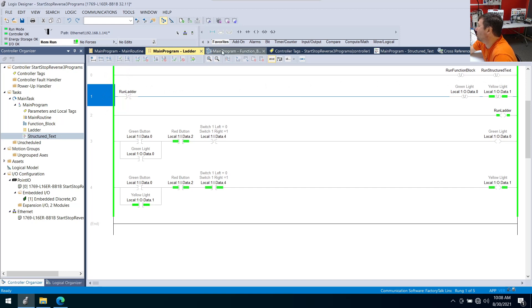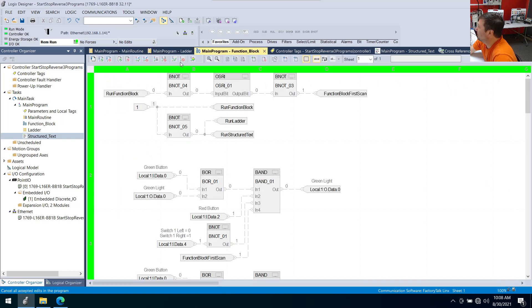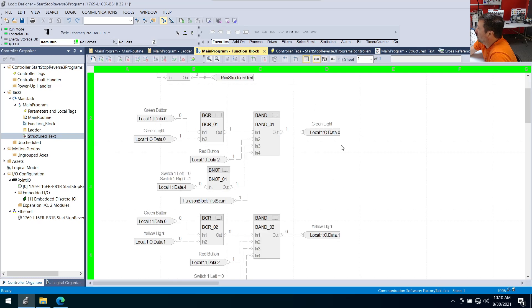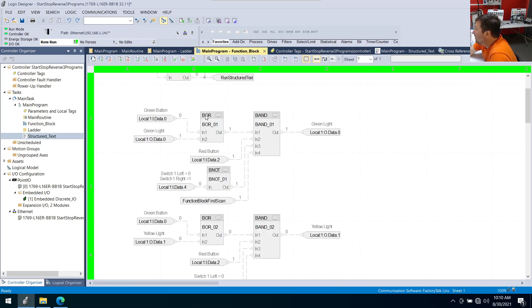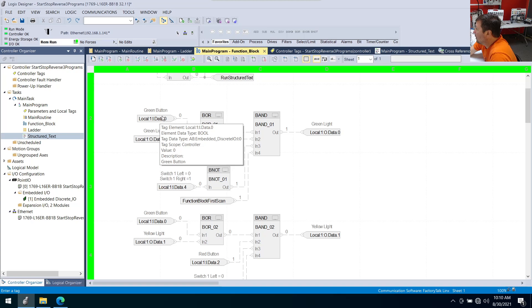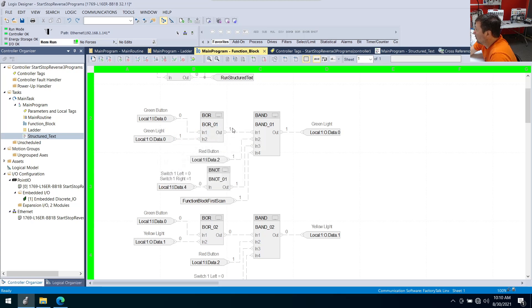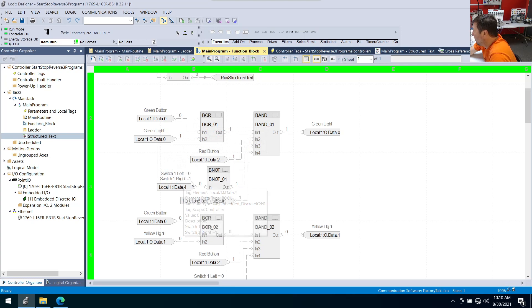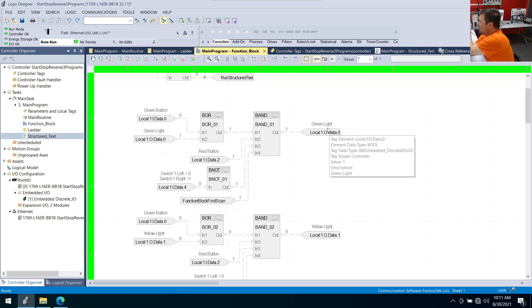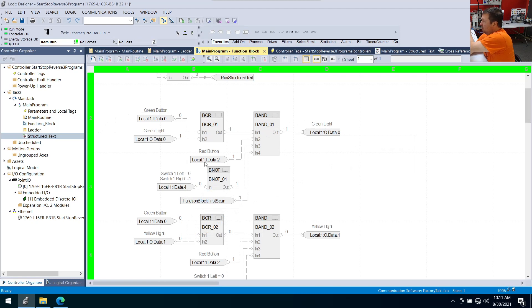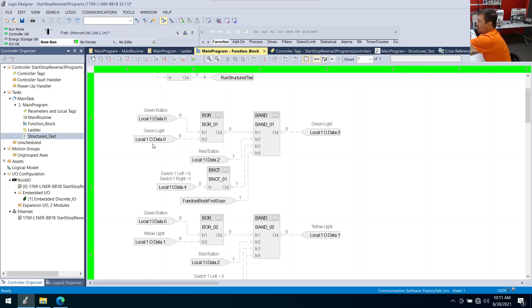Now let's look at our function block routine. So here's the function block logic, and let's skip over this first one for now. And right here is our green light logic. So right now we have a one in our green light because we're still running the ladder routine. If I go over here to our main routine, you can see I've got switch four in the left position. So if the green button or the green light is on, we're going to get a one here. And then we're looking for that and the red button and not switch four to the right position, and then not this first scan block. And so when I switch over to function block with switch four, you're going to see the green light go out. So there it goes out. And now we press the green button. Our green light comes on.